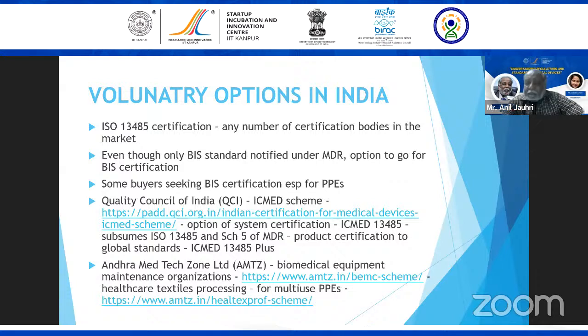Fine, that's fine. Then in Quality Council of India, in fact, I was involved, Mr. Satyendra was also involved. We have a scheme called ICMED, Indian Certification of Medical Devices. This was created even before MDR came, and its primary purpose was to demonstrate that Indian medical devices can comply with global standards, not with BIS standards, global standards. It has components of system certification, ICMED 13485. And ICMED 13485 has one advantage. It subsumes both Schedule 5 and ISO 13485. So if you get an ICMED 13485 certificate, you get both in one. Otherwise, today, if you get a 13485 certificate, you are still not compliant with Schedule 5 because there are certain differences. And if you get audited for Schedule 5, you are still not compliant with 13485 because there are differences. But if you get ICMED 13485, you are complying with both.